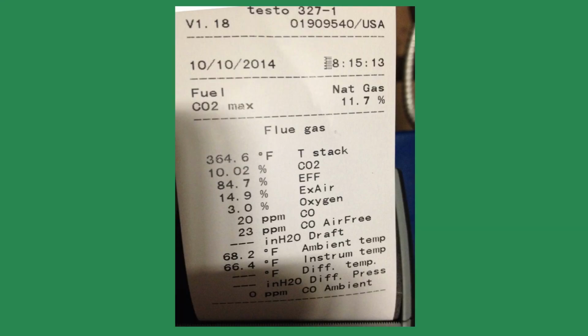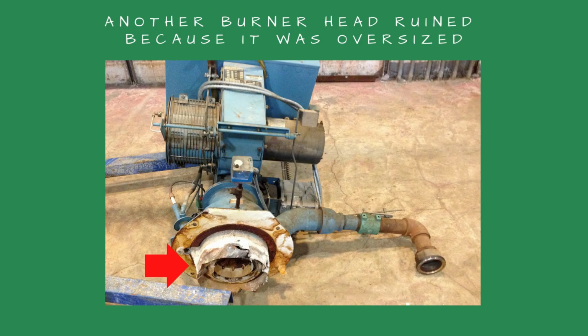The boiler was originally oversized for the building. I discovered the hydronic loop for half the building was disconnected because the owner installed a packaged rooftop unit that provided both heating and cooling. This meant the boiler, which was already oversized, was now more than double the size.